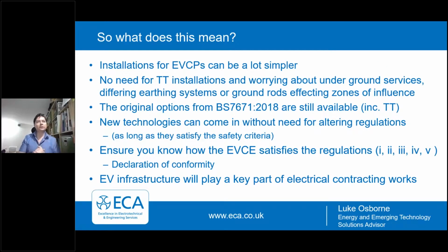So what does the rollout of EVs mean for your businesses, and what does the change in Amendment 1 mean to you guys? Well, installations for electric vehicle charge points can now be a lot simpler. There's no need for TT installations or worrying about the underground services, the differing earthing systems, or the ground rods affecting zones of influence. The original options from BS 7671 are still available, including TT, as I mentioned. New technologies may come in without the need for altering regulations, as long as they satisfy the safety criteria.